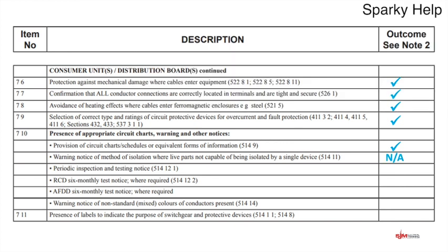Look, warning, multiple supplies. Isolate all electrical supplies before carrying out work. Isolate the mains at, and isolate the alternative supplies at. So you're looking for something like that to warn somebody that actually just turning this off doesn't mean that it is dead. If you haven't already got alternative supplies, then it's probably going to be an NA. If you have got alternative supplies, you'll probably put a tick there.